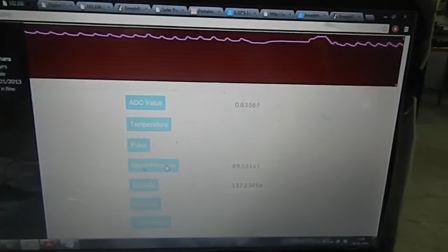Now I'll further reduce the pressure, and it will now calculate the diastolic pressure. Diastolic pressure will come when the oscillations will start to die. This is the diastolic pressure that the algorithm has calculated. This shows that the values that we have obtained for the systolic and the diastolic pressure are in close measure with the values that we obtained with the electronic blood pressure meter.